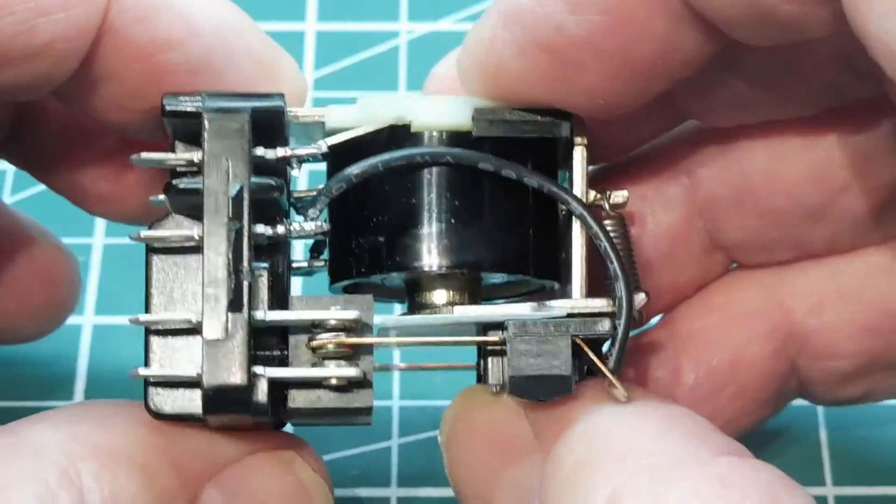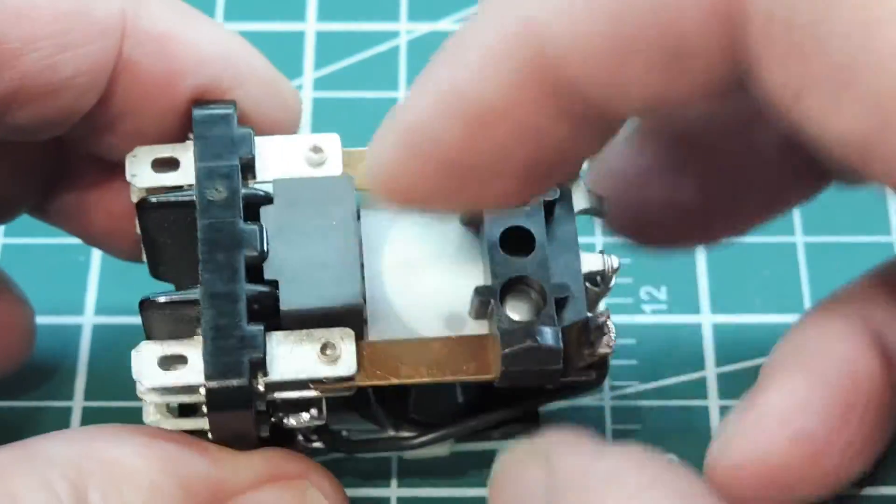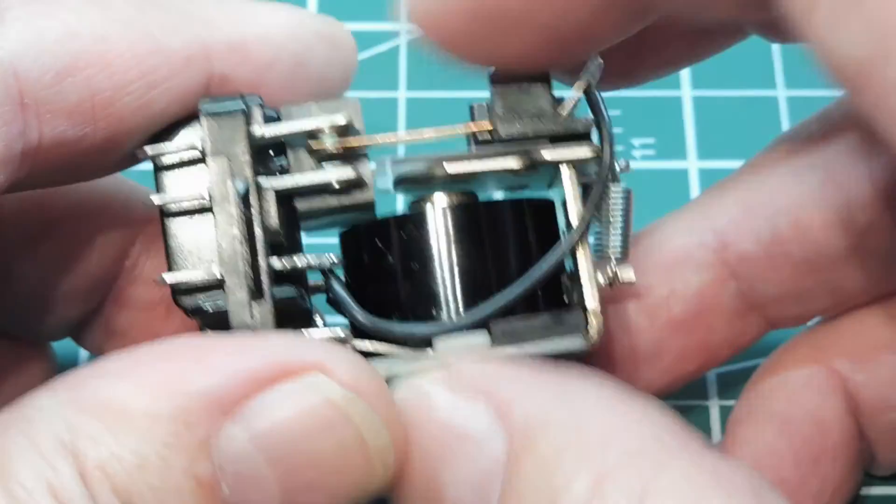And that will extend the contact life of the relay. So that's one way that they've solved the problem of burnt contacts on relays, is to use a magnetic field to interact with the plasma.